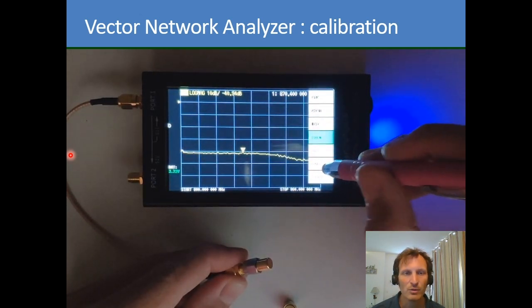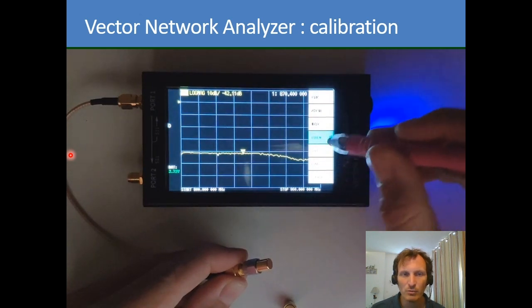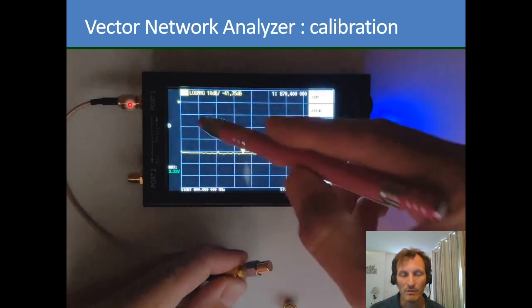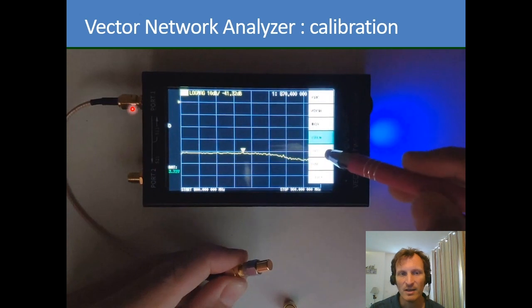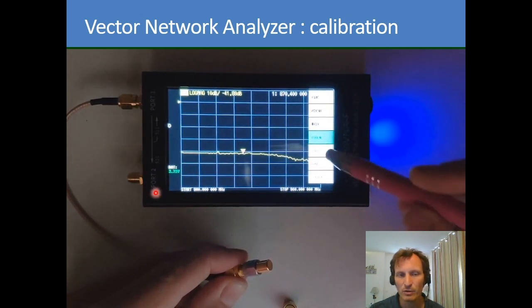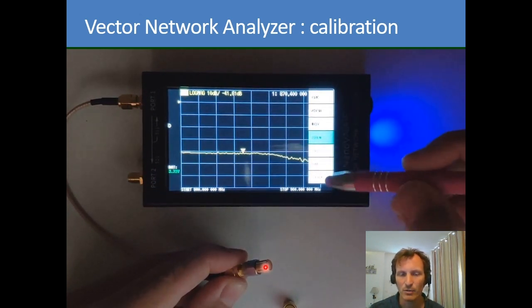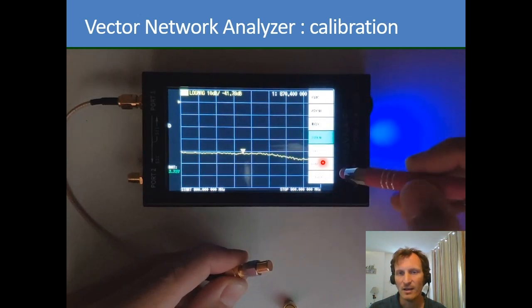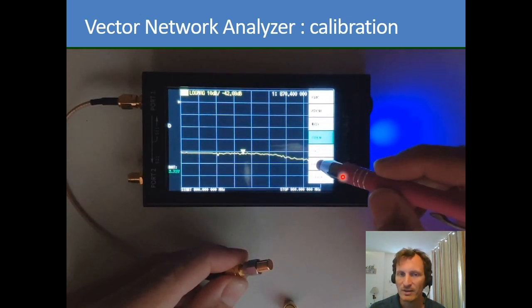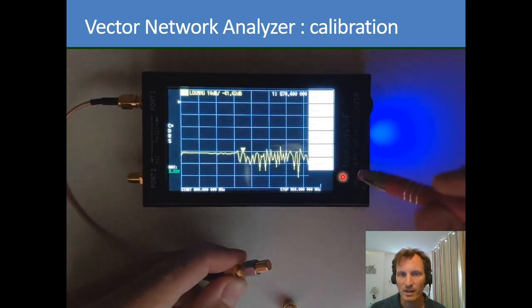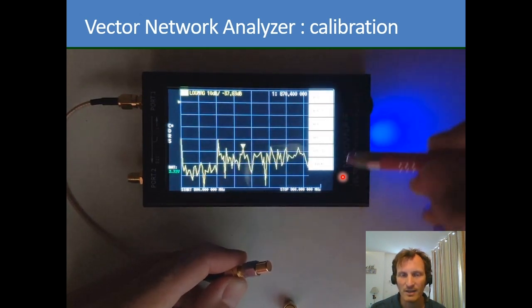So of course, here you see we are doing a one port calibration. We have just port 1 which is calibrated. If you want to calibrate the two ports, you will also need a second cable to connect the two ports together and click on through. But even if you are doing just a single port calibration, you can click on done and it's okay.